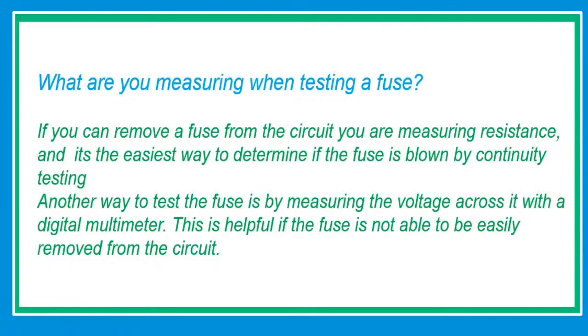Sample answer: if you can remove a fuse from the circuit, you are measuring resistance, and it is the easiest way to determine if the fuse is blown by continuity testing. Another way to test a fuse is by measuring the voltage across it with a digital multimeter. This is helpful if the fuse cannot be easily removed from the circuit.